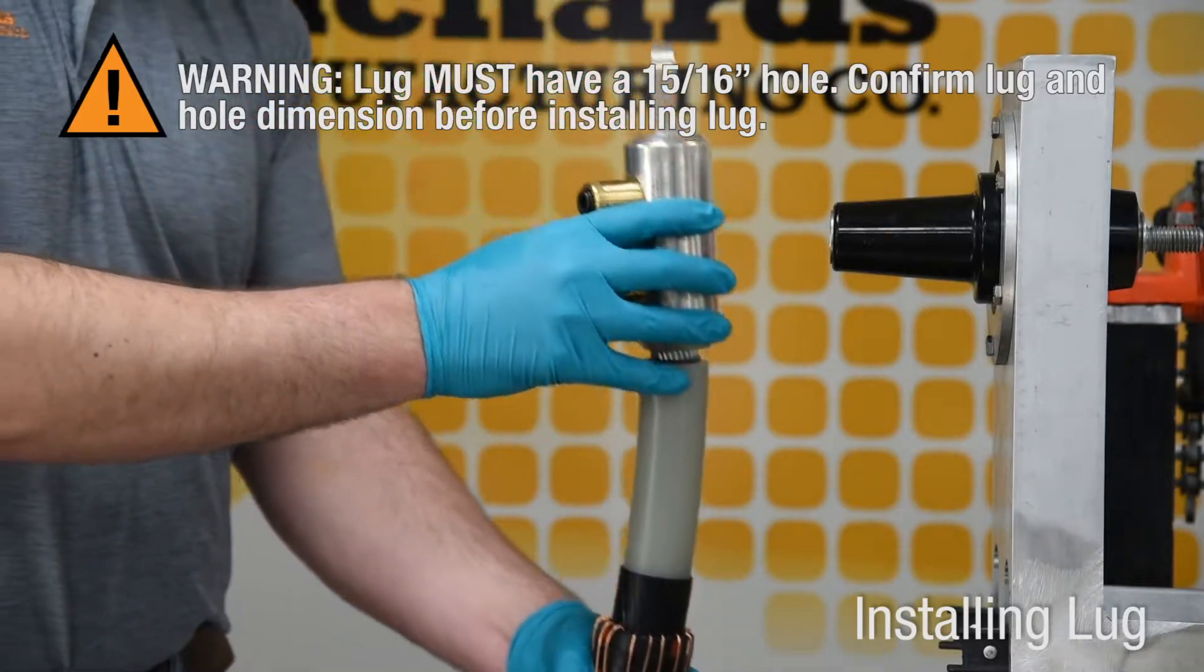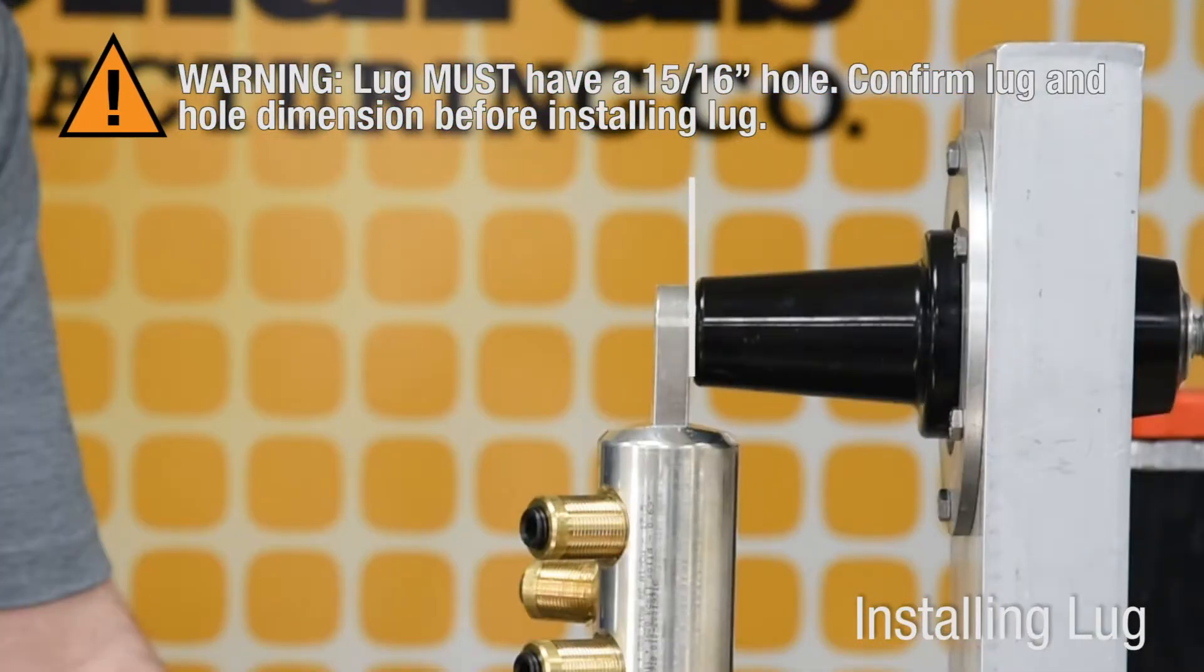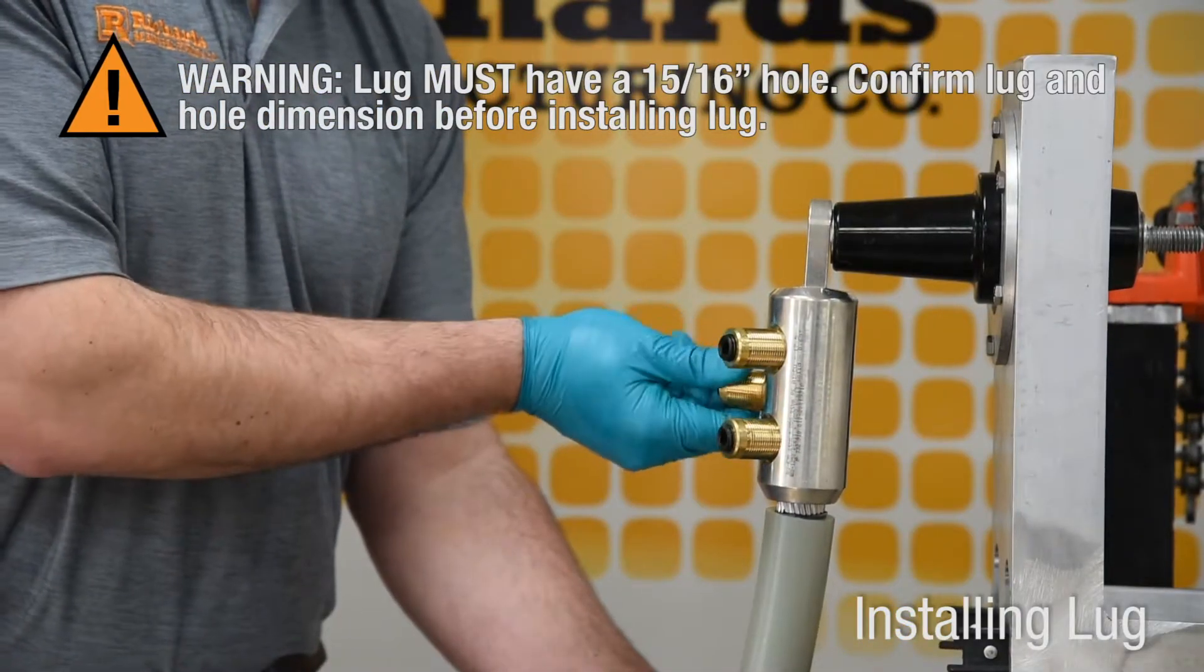Before installing the lug, make sure the spade of the lug is parallel to and aligned with the mating component. The conductor must be fully seated inside the barrel.